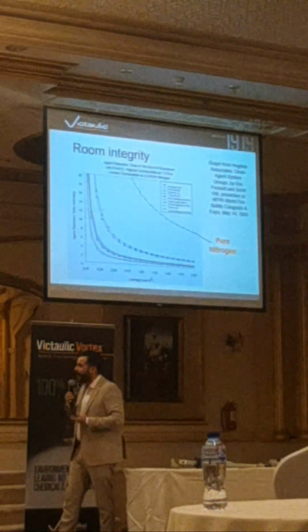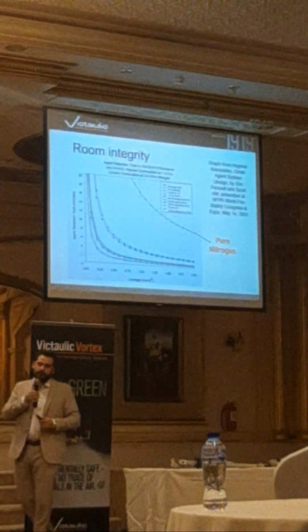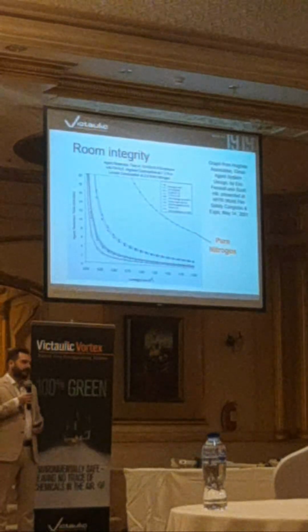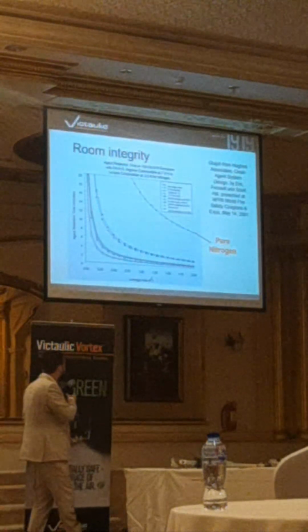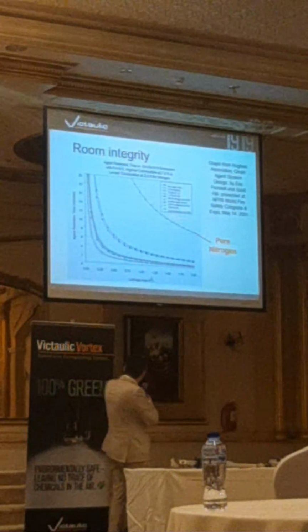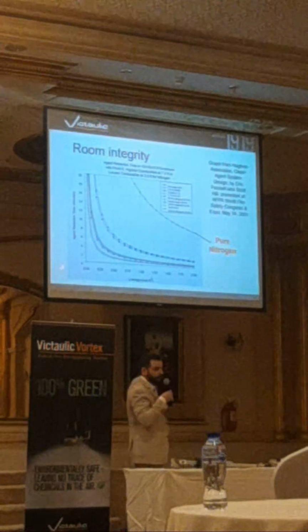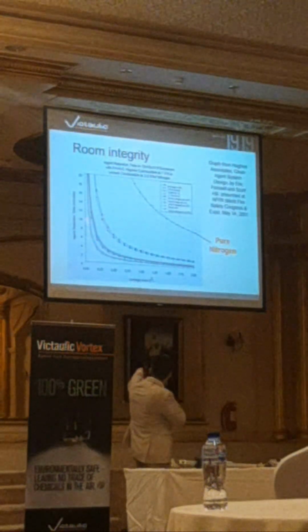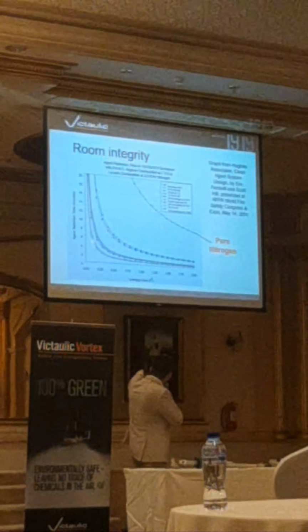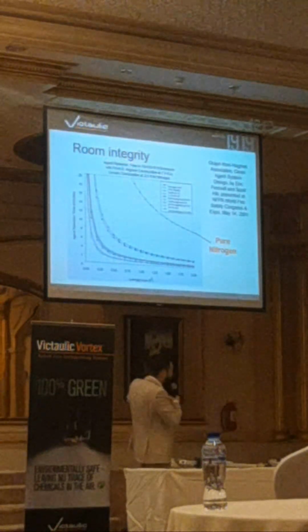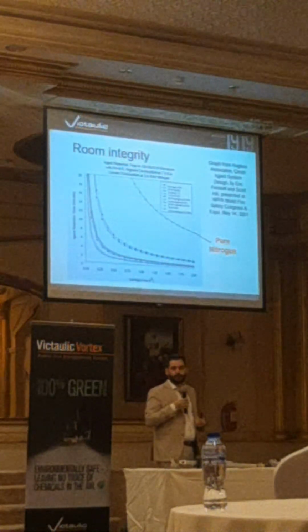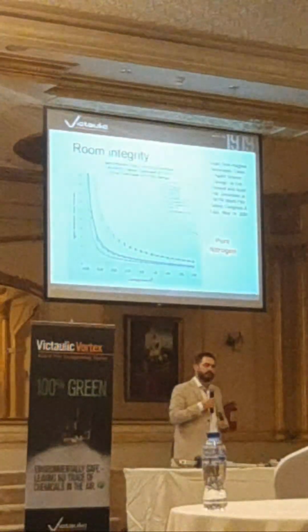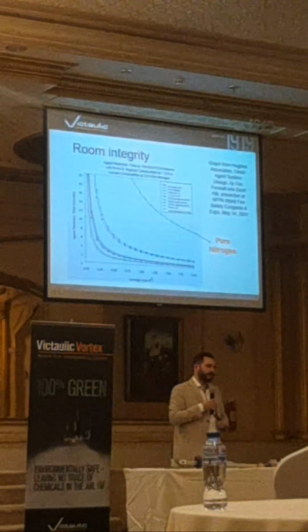You can see how important it is to close off your room completely. The lowest line here is FM200, and you can see that with the slightest amount of opening, it immediately drops the retention time. That's why it's so important to completely close off your room to have a sealed environment.